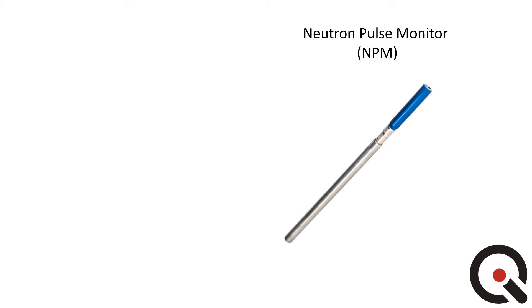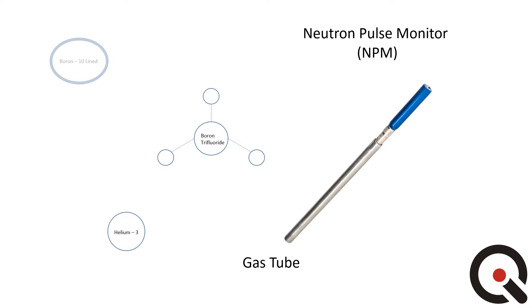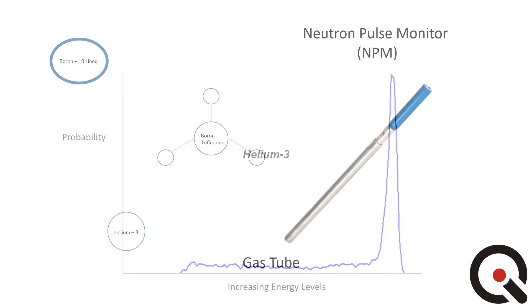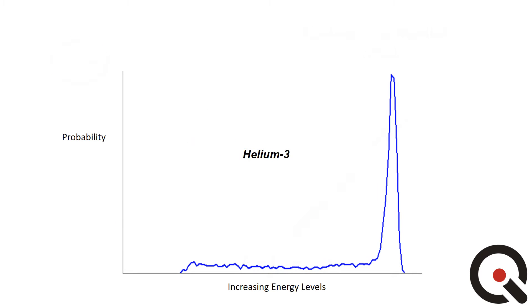The NPM works by attaching to a proportional neutron detector, which consists of a tube filled with either helium-3 or boron trifluoride gas, or a tube lined with boron-10. This measures and logs the proportion of neutron events that occur at various energy levels within the tube.